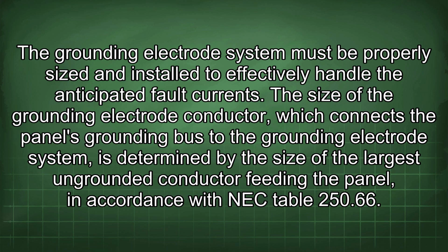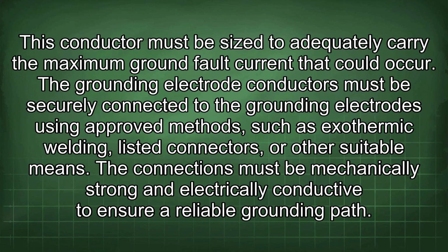The size of the grounding electrode conductor, which connects the panel's grounding bus to the grounding electrode system, is determined by the size of the largest ungrounded conductor feeding the panel, in accordance with NEC Table 250.66. This conductor must be sized to adequately carry the maximum ground fault current that could occur. The grounding electrode conductors must be securely connected to the grounding electrodes using approved methods such as exothermic welding, listed connectors, or other suitable means. The connections must be mechanically strong and electrically conductive to ensure a reliable grounding path.